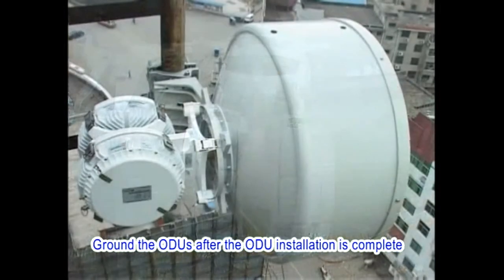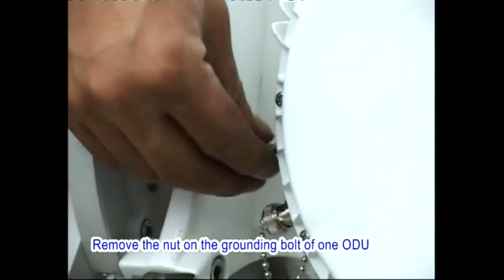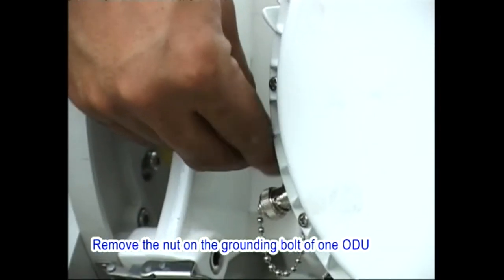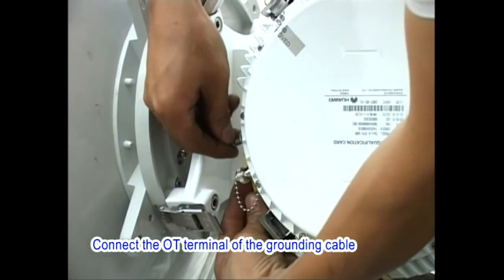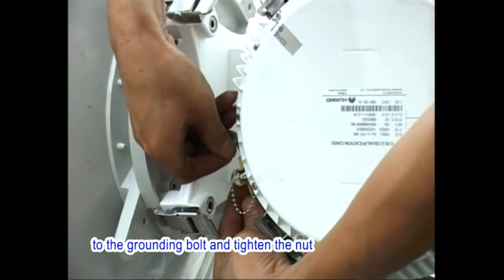Ground the ODUs after the ODU installation is complete. Remove the nut on the grounding bolt of one ODU. Connect the OT terminal of the grounding cable to the grounding bolt and tighten the nut.